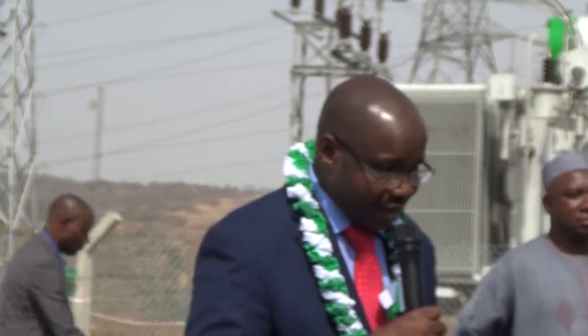We added it to the existing transformer capacity in Katampe. The existing capacity in Katampe was 120 megawatts. With this addition of 100 megawatts, the capacity of Katampe has increased to 220 megawatts. With that development, we have met the N-1 criteria here in Katampe, meaning if one transformer fails, the society will not feel it. Abuja Disco will not lose electricity because one of them has failed.